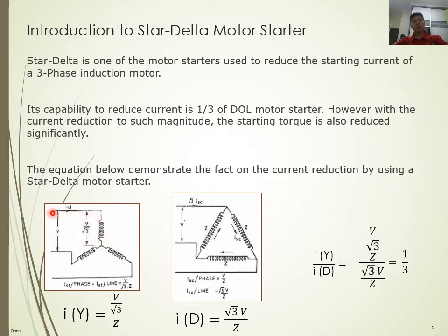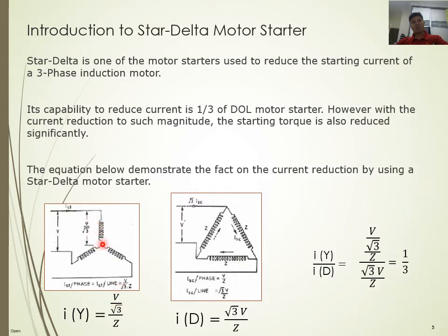For the current, the line current and the phase current are equal — only the voltage differs in star connection. So the line-to-line voltage is 415V and the phase voltage is 240V. By reducing the voltage at the phase, we can reduce the current flowing through this circuit during starting. The phase voltage is V over root 3, divided by the impedance Z of the phase, giving a certain current value.